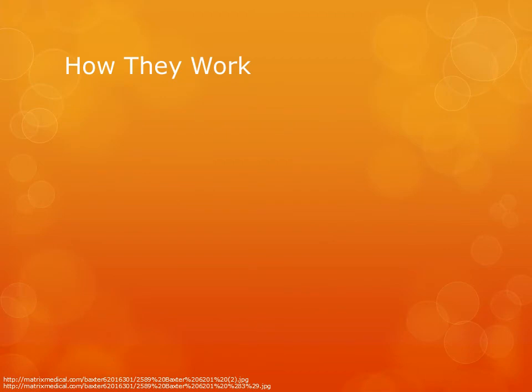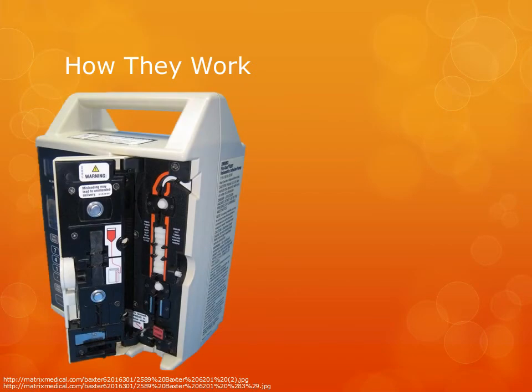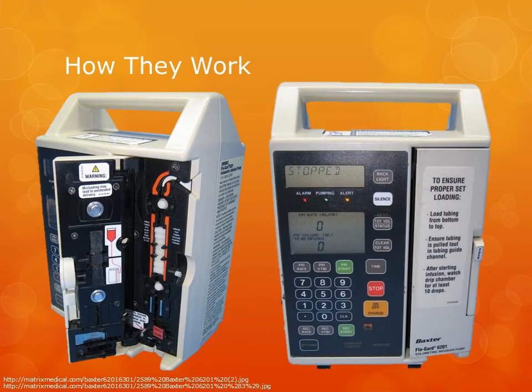We'll be going through today a simple peristaltic single-channel device by Baxter, which we saw briefly before, because this is the device that most hospitals or home users will actually utilize. So as you can see here on the left, this is with the door open on the device, and where the IV line is placed, it is pushed down through the little peristaltic clips and through two pressure sensors on the top and bottom. Once it's all inserted, this door is closed and you get to the main panel, which is at the front here.